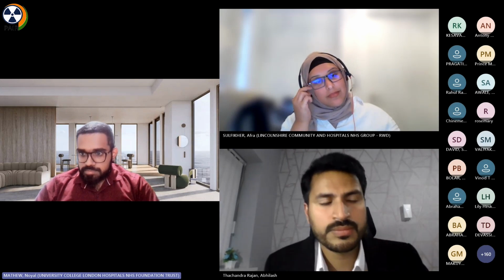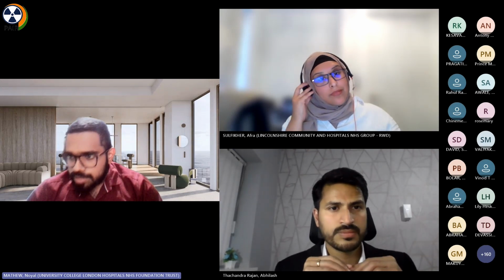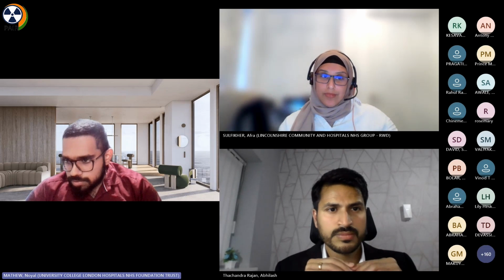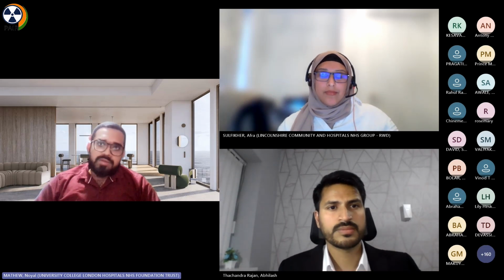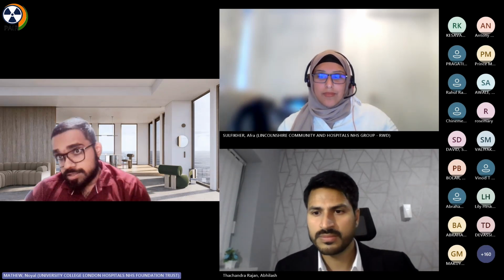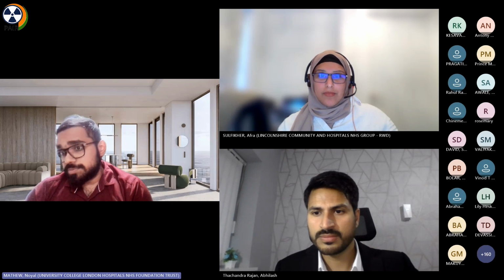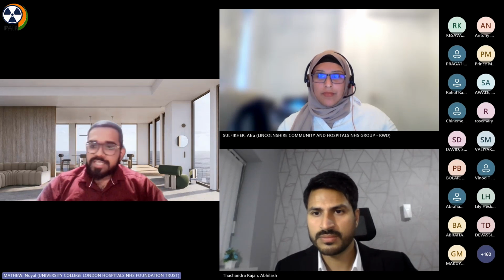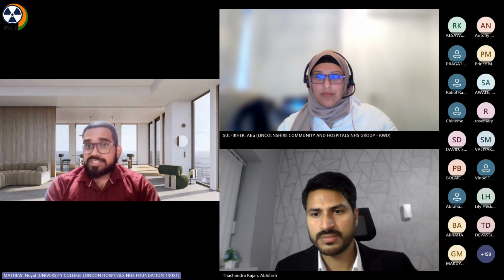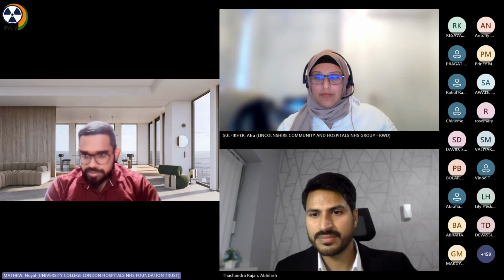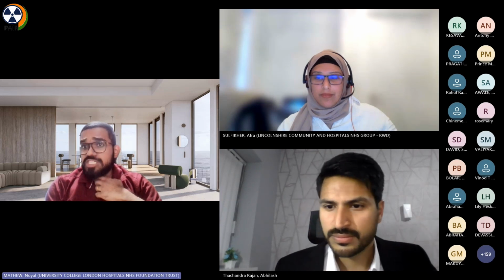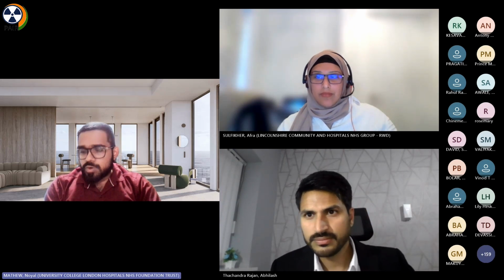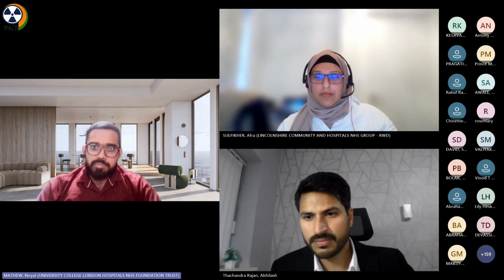And regarding off-label scanning, I'm not really sure if I have understood this. Off-label would be if you do not have any conditions on the manufacturer's website, then that would count as off-label scanning. Not that you can't do it, but I think it's something that needs risk assessment. You need to sit down with your physicist, try to see the rationale behind the scan, come up with a protocol regime, and do it in a controlled way. So that is possible and doable, provided you have some kind of support.